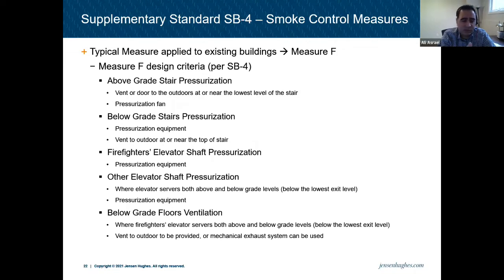A typical door is typically a 1.8 square meter opening. So if that's not sufficient, you've got to add louvers on top of it and dampers and all that. But typically 1.8 square meters is what you see unless the building is very tall. Below grade, same requirement. You add a fan, the same requirement as measure A, and a vent at the top of it. So when you're pressurizing from the bottom, you vent it at the top, and when pressurizing at the top, you vent it at the bottom. So you maintain that flow within the shaft.